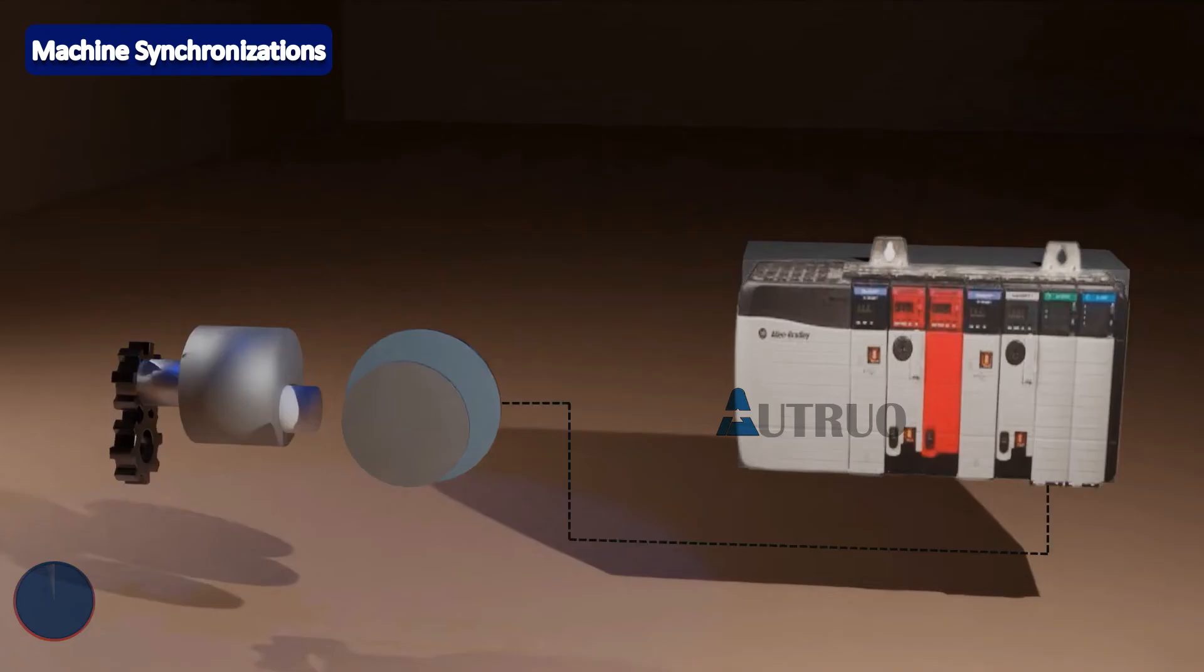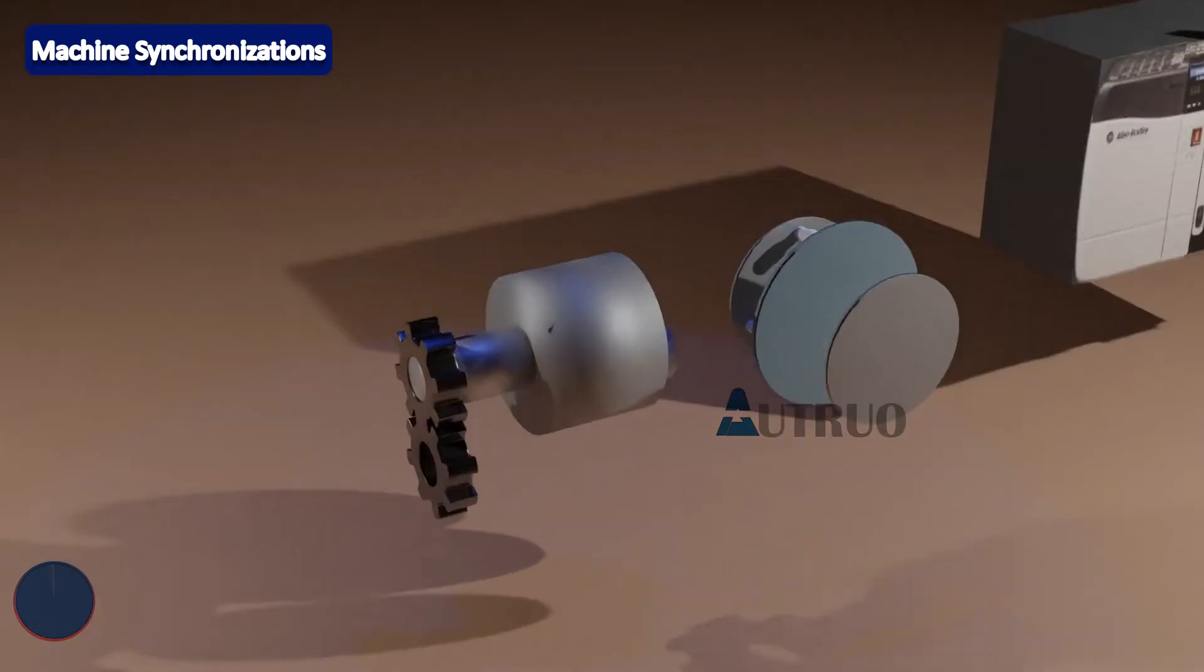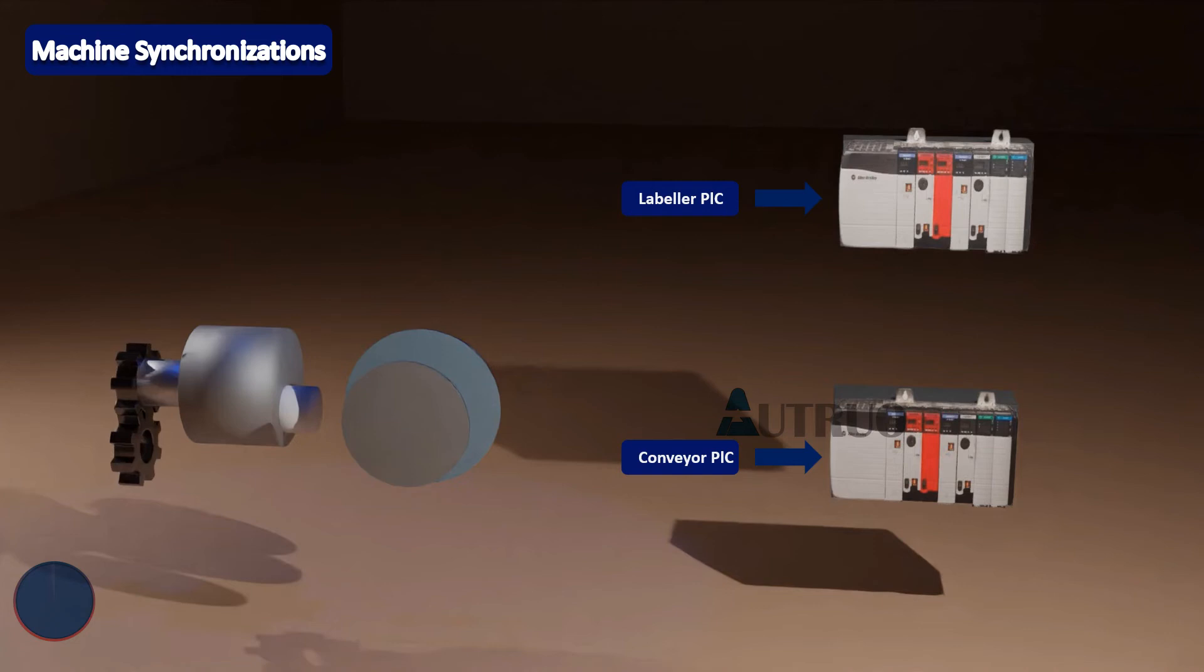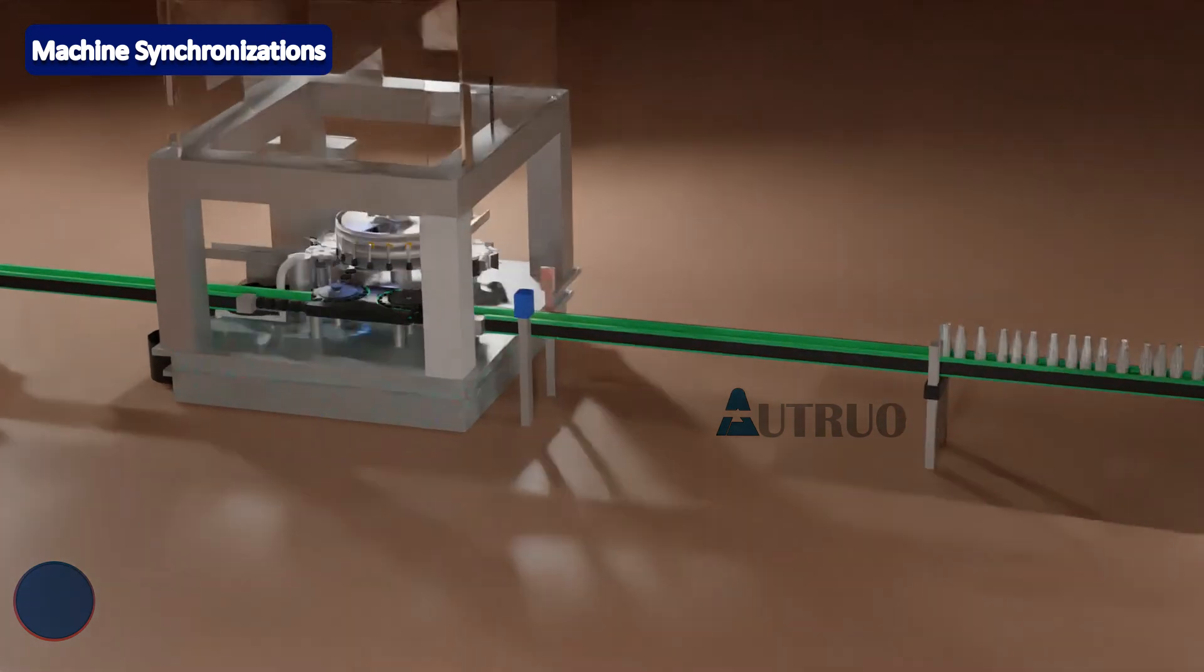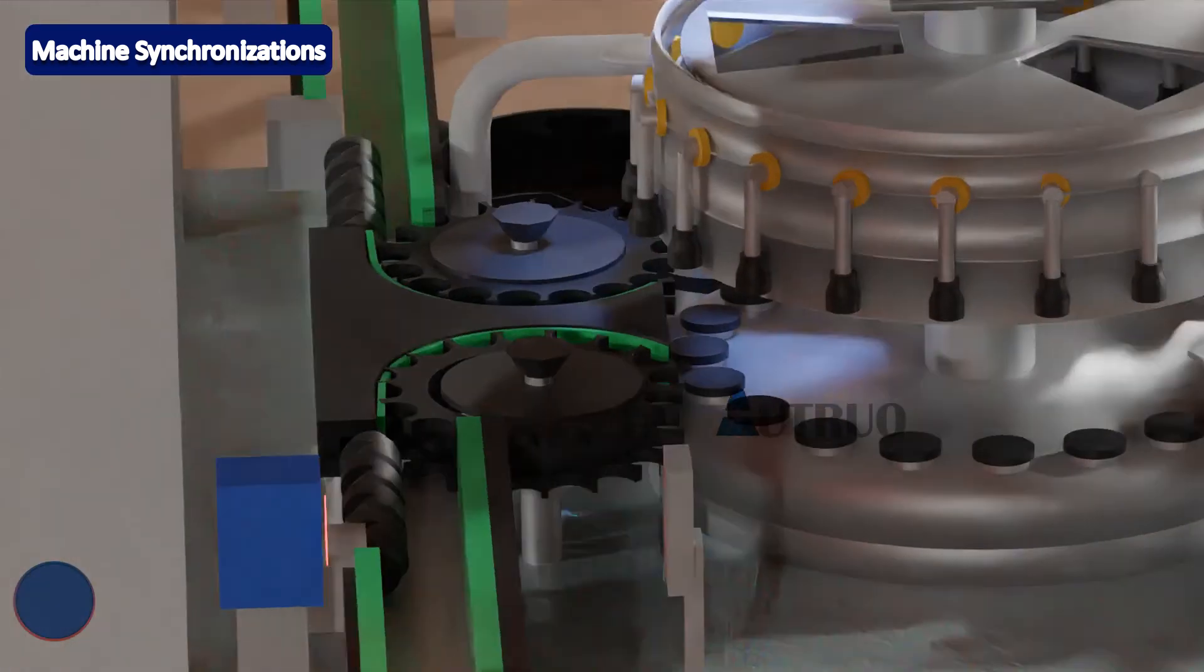This means apart from the fact that the encoder signal is transmitted to the machine PLC, the signals are also shared with external machines. And in this case, we are dealing with a conveyor system. The signal sent to this machine will be used by the PLC of the conveyor system to either speed up the conveyor in relation to the lead machine or vice versa.